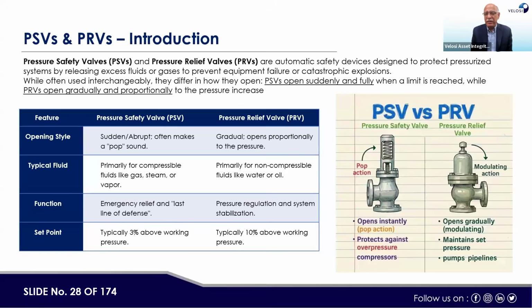So in that scenario, pressure may increase for the system. If the pressure for the system keeps increasing, it may lead to the burst or failure of that particular mechanical equipment or mechanical system. To avoid that scenario, PSVs and PRVs are installed. For liquid service, a PRV would be installed, and for gas or vapor service, a PSV would be installed, and there would be a set point for these valves. As the set point is crossed, the PSV or PRV will lift and the extra pressure can be released.